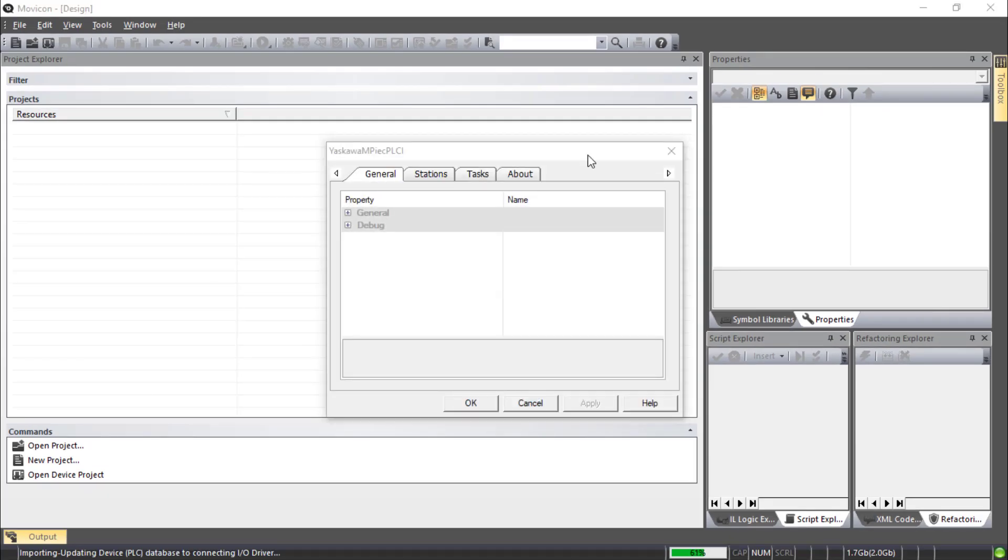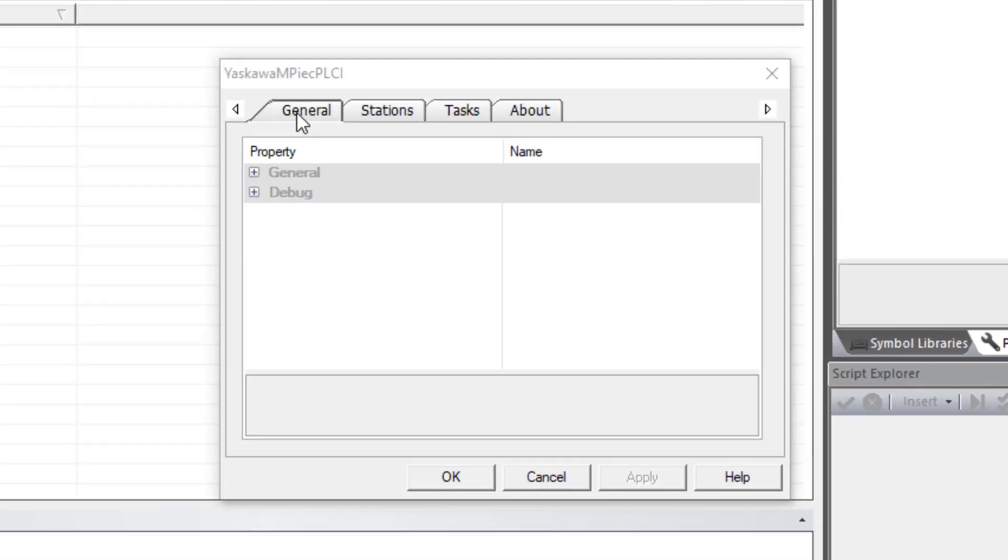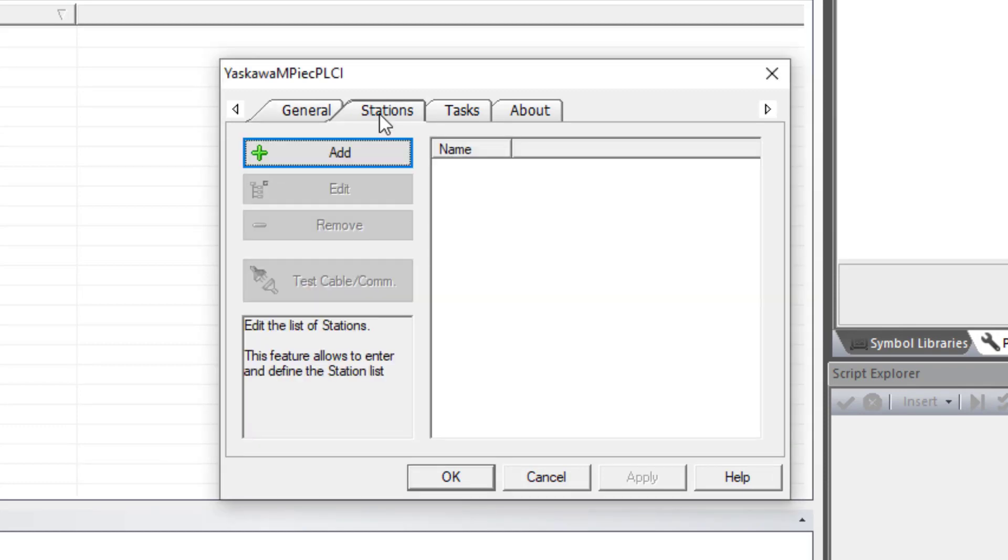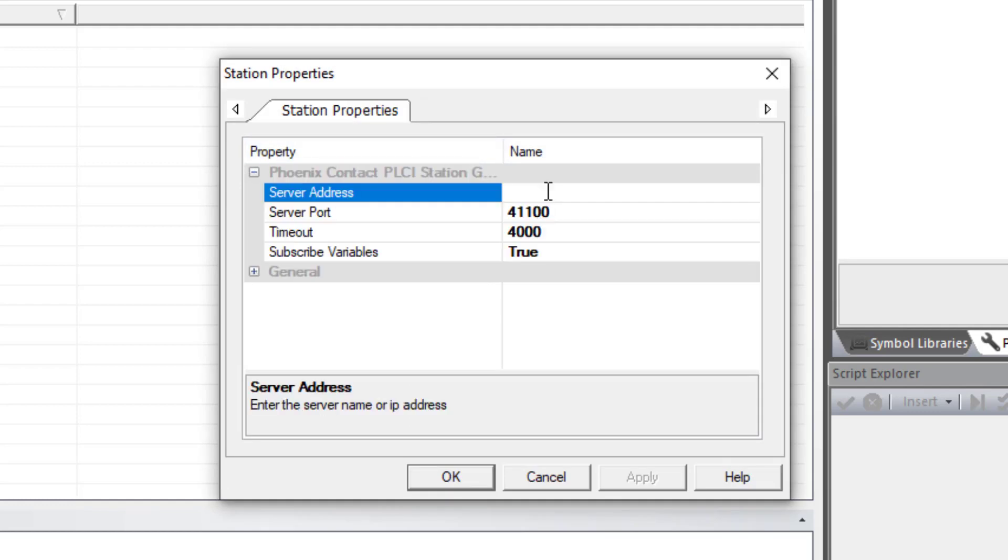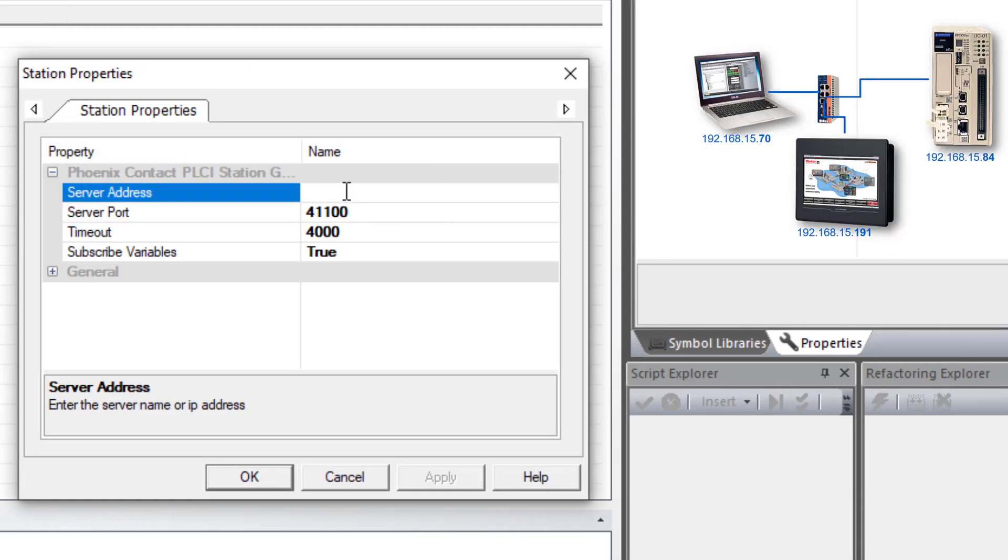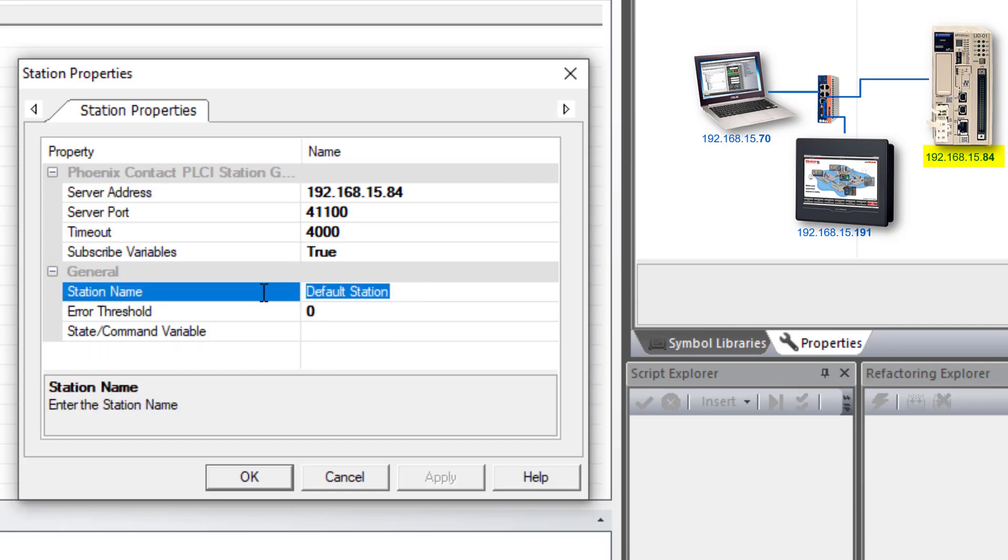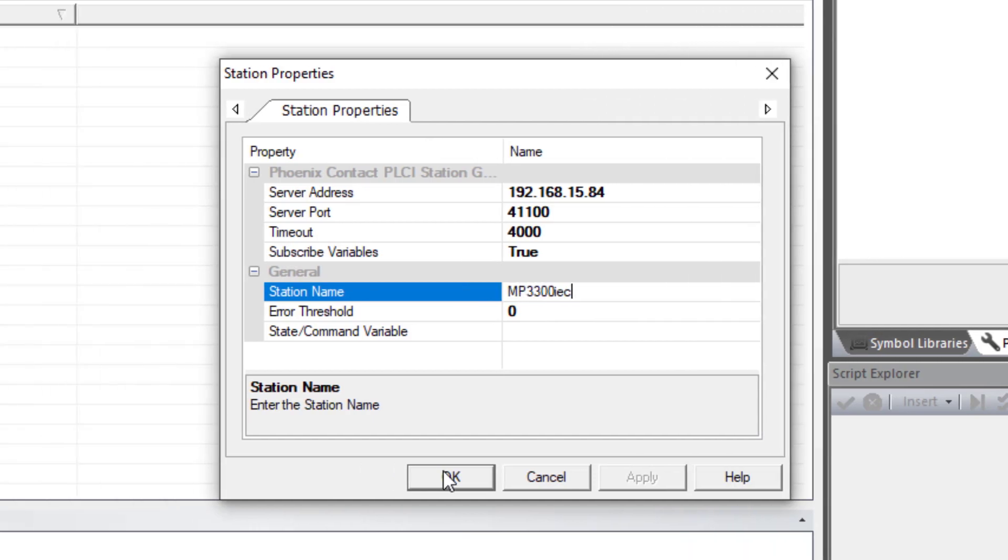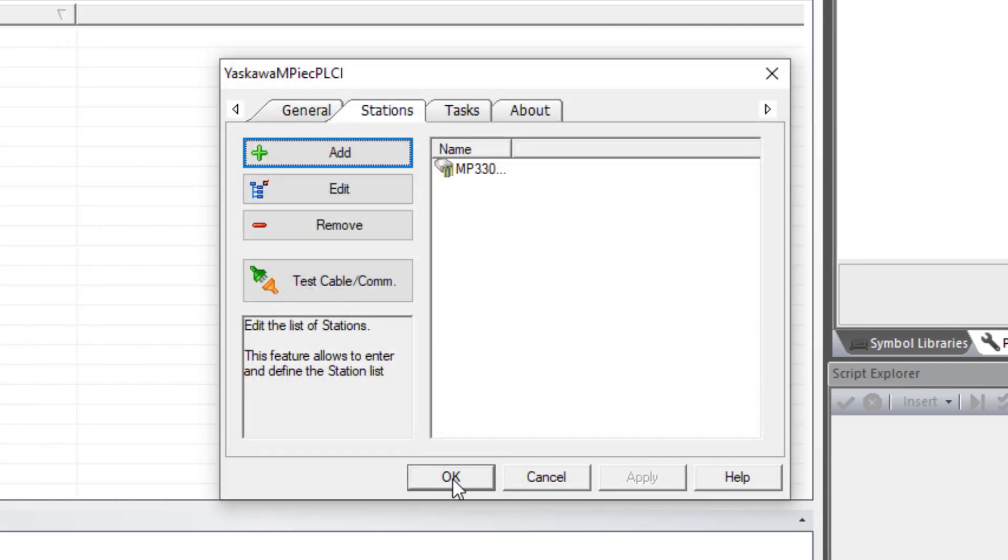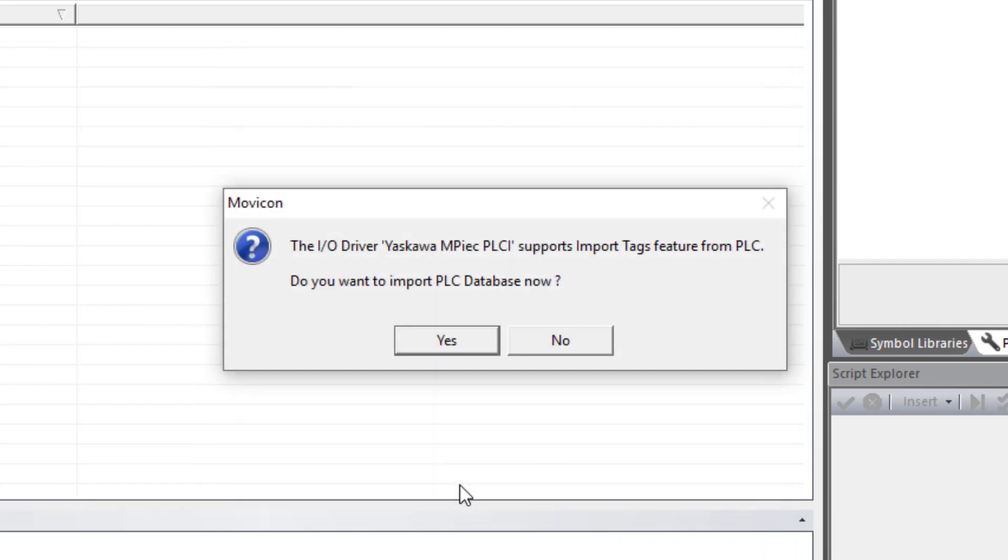The next window to appear is to set up the PLCI driver. You don't have to change any of the general properties. But the MPIEC controller is considered a station. Let's go to stations and add and expand to type in the server address. The address of the controller was 192.168.15.84. That's the controller, not the HMI. And under general, just change the name to whatever name you want for that controller. I'll just call it MP3300iec and OK. And OK, that's it.